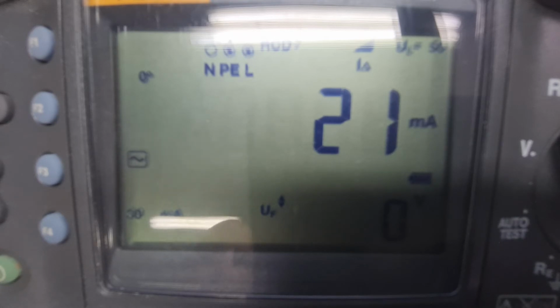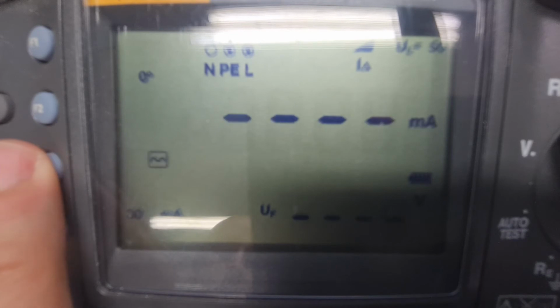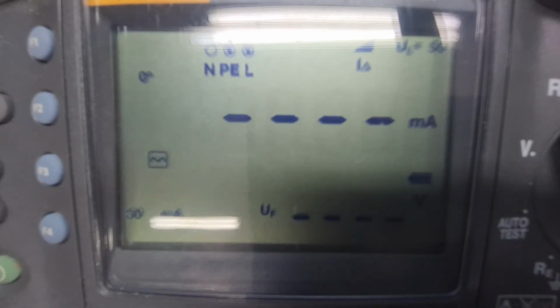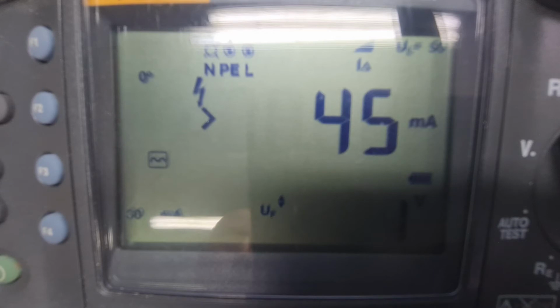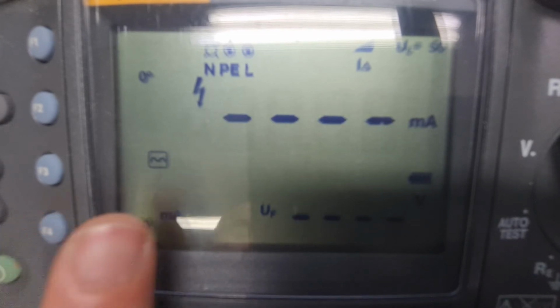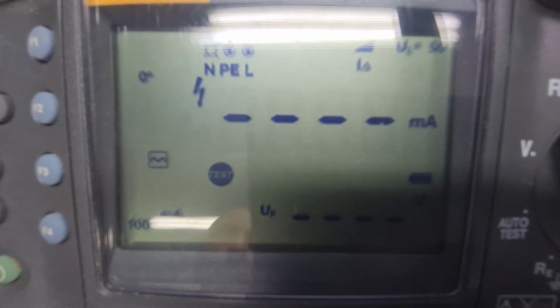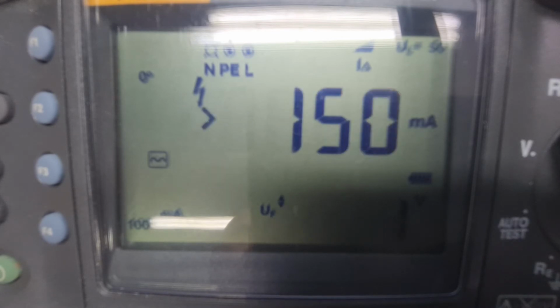Now the next step is that we are going to test for DC ripple current. I'm going to arm the system as before. I get the power on sign. I press test and wait to see what happens, and the instrument is telling me that up to 45 milliamps I am not getting an RCD trip. So I'm going to go into the next setting, which is 100 milliamps, and test again and wait a few moments to see what happens, and once again I have no trip even when there is a DC ripple current of 150 milliamps.